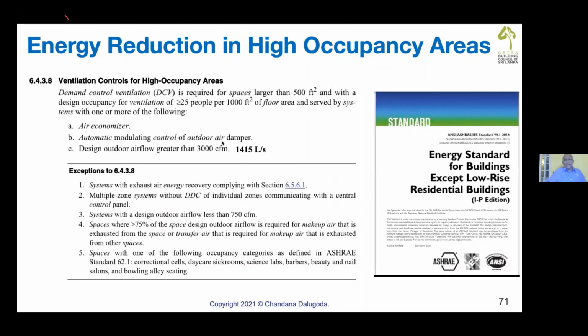And also in buildings we have highly occupied areas like banquets, the seminar rooms, high occupation. That is called high densely populated area. We call that 25 people per 100 square meters. Such areas, you should use an energy reduction method called demand control ventilation. If you are using outdoor air over 3000 CFM or 1400 liters per second, you need demand control ventilation.